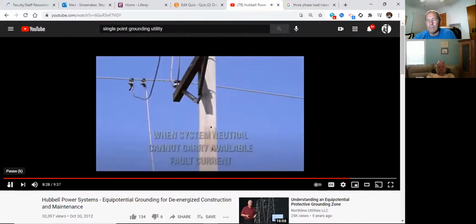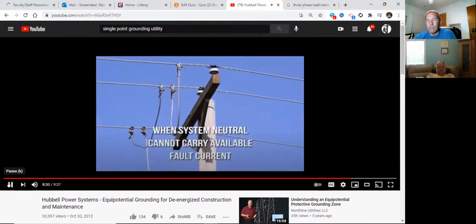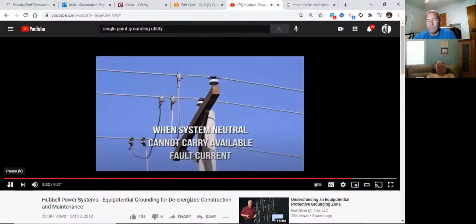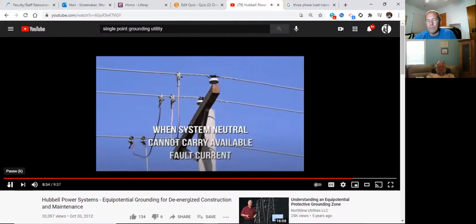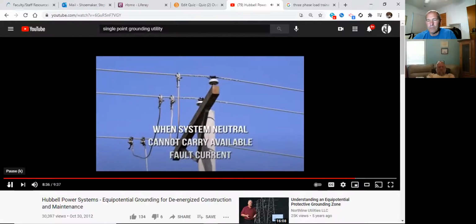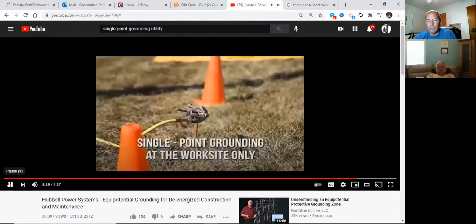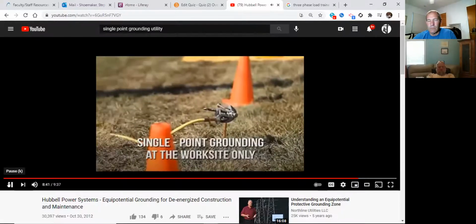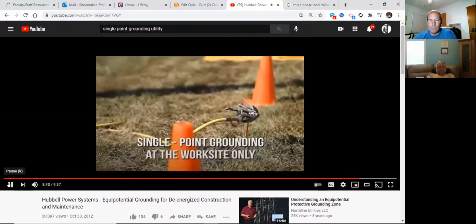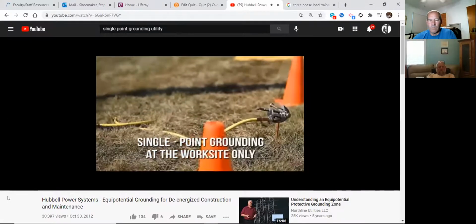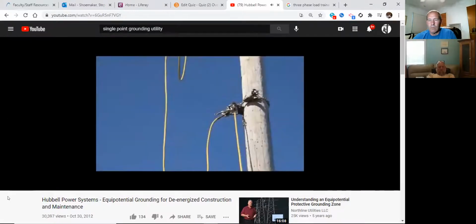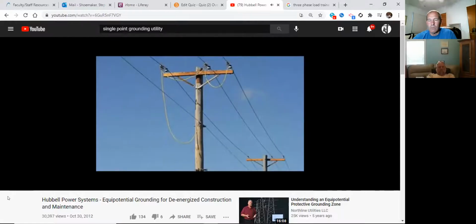And another lead from the cluster bar to the first phase. This alternate setup takes no more leads than the first way shown, with a lead from the cluster bar to the neutral and another from the cluster bar to the phases. Another way to establish an equal potential zone employs single point grounding at the worksite only, with leads from a screw ground rod to a cluster bar, the neutral, and all three phases.